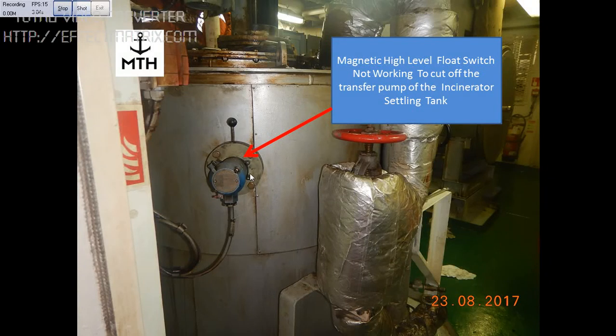This picture shows the magnetic type float switch which was used for stopping the transfer pump of the incinerator settling tank. When the level comes to this position, the pump was not stopping. We are going to investigate why this float switch didn't work.